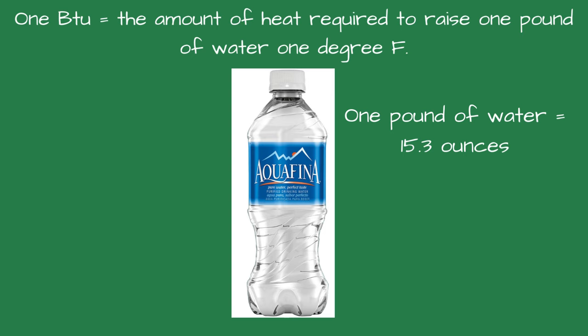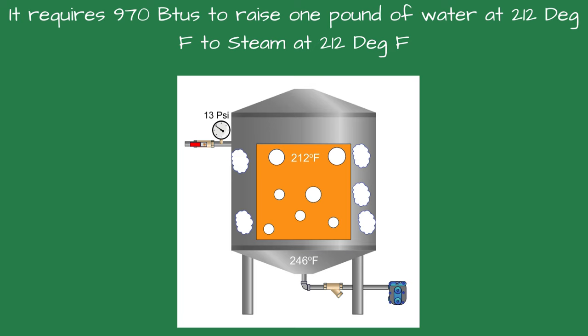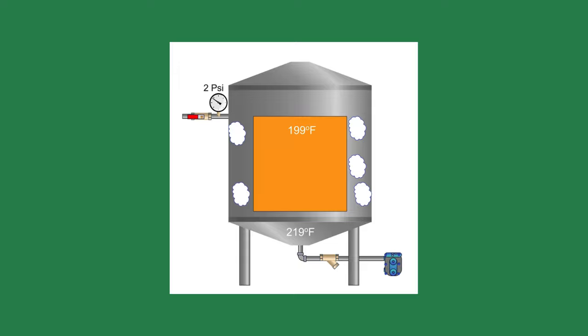The real challenge to getting a rolling boil is when the water temperature reaches 212 degrees Fahrenheit. It requires 970 BTUs to change 1 pound of water at 212 degrees to steam at 212 degrees — this is the latent heat. At 2 psi, the steam temperature is 219 degrees, or just 7 degrees above the 212 degree design temperature.